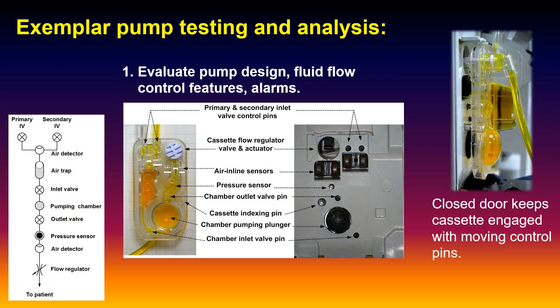One of the other things I looked at, these cassettes also have a little valve. It's like a little faucet valve that allowed the nurses to do a fast flush if needed. With the pump cassette not in the pump, you can just turn the little knob and control the flow. I characterized how that behaved and found out that in less than 1/8 of an inch, you could go from completely obstructed to almost a free flow condition, 800 mLs per hour. That's really moving.